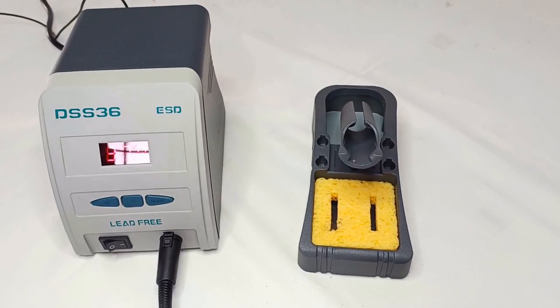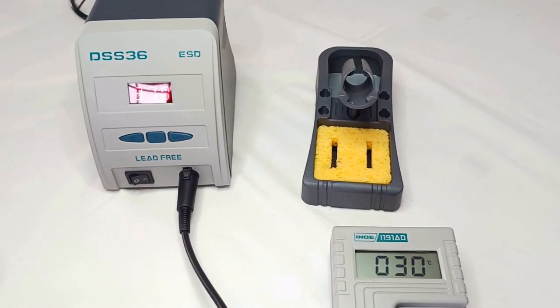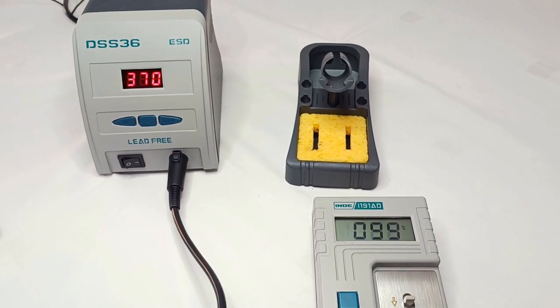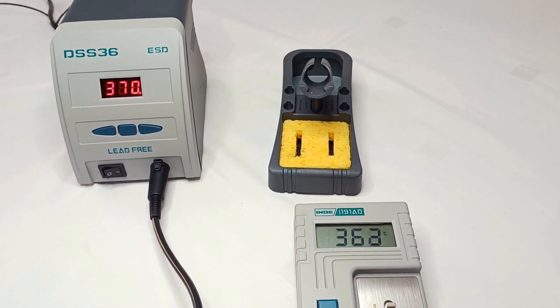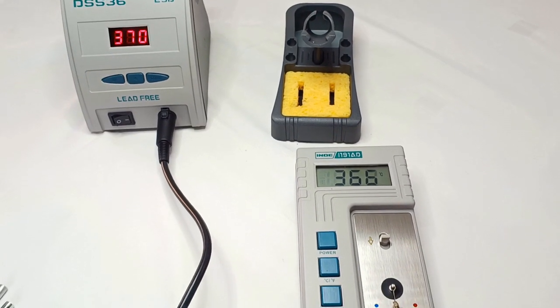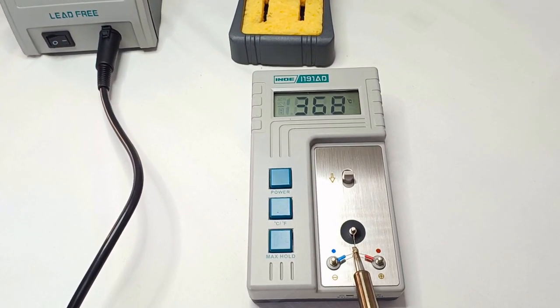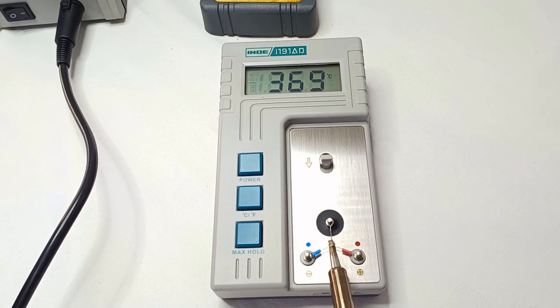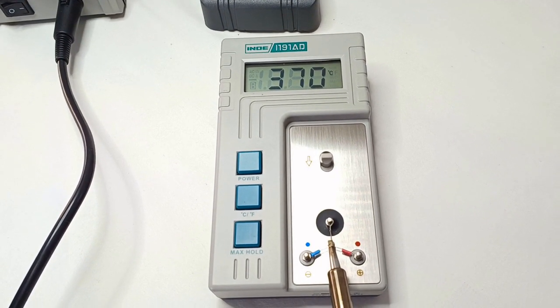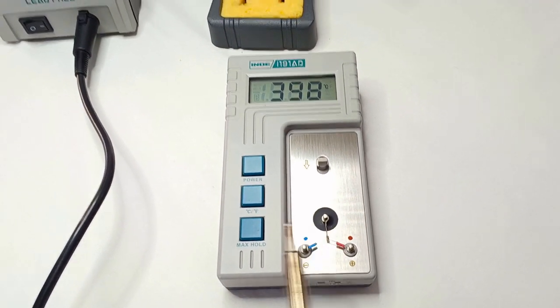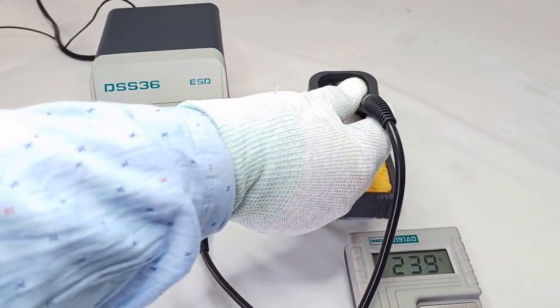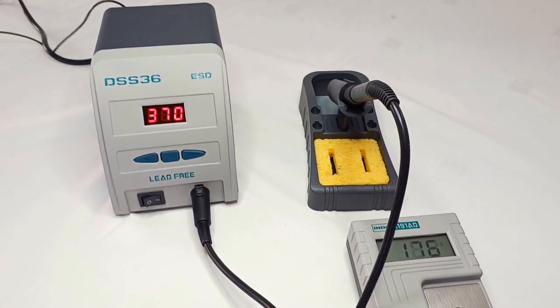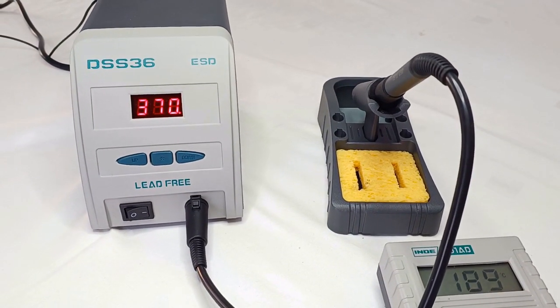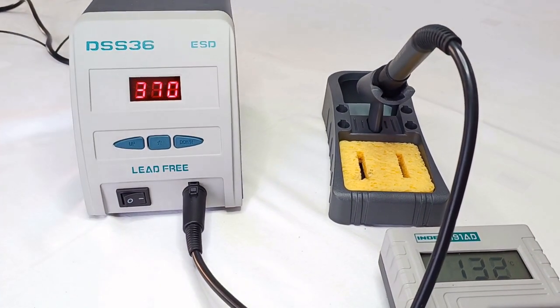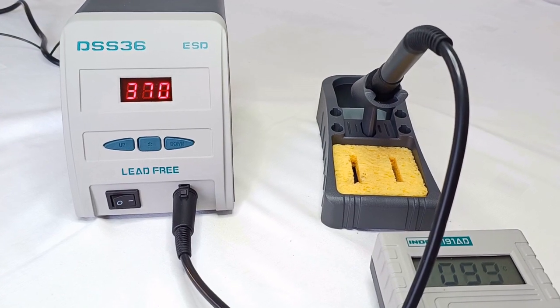Then we will again verify whether the input value we have entered into this control unit is appearing on the external calibrator or not. See, earlier the measured value was 368, now the value is close to 370 degrees. It means the value which we have entered into the control unit has been accepted, and now the set temperature and the actual temperature are almost the same. So this is a clear advantage of the calibration feature.